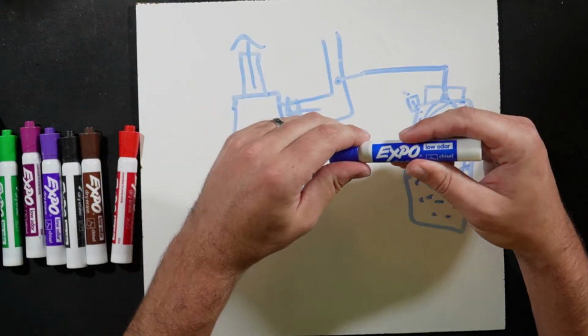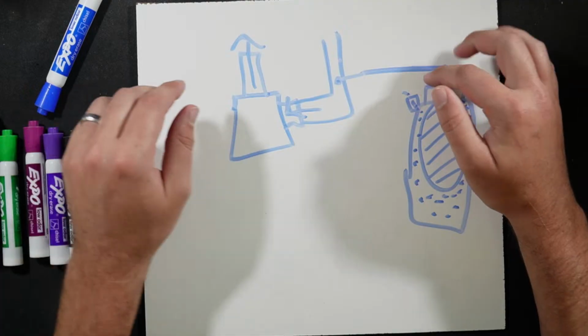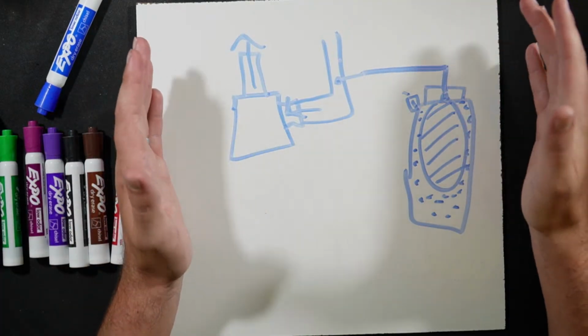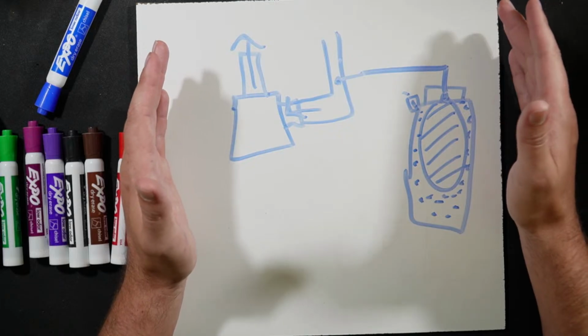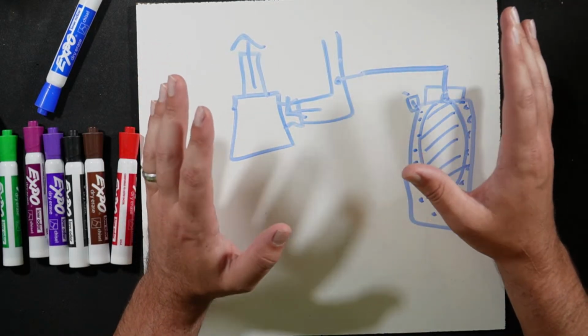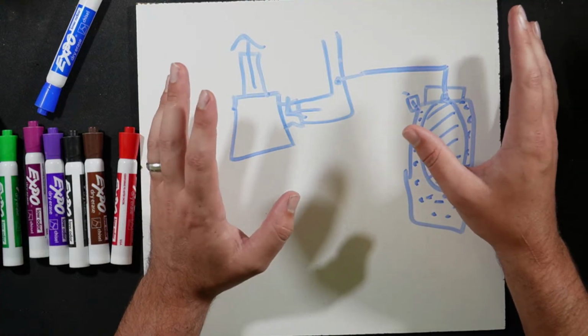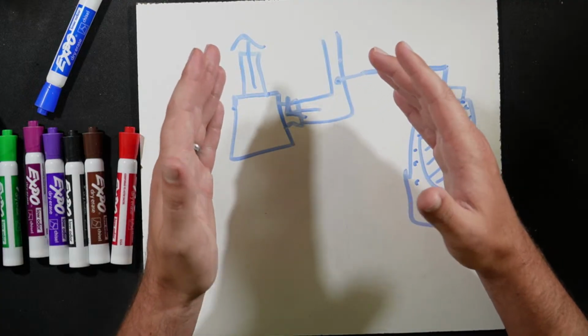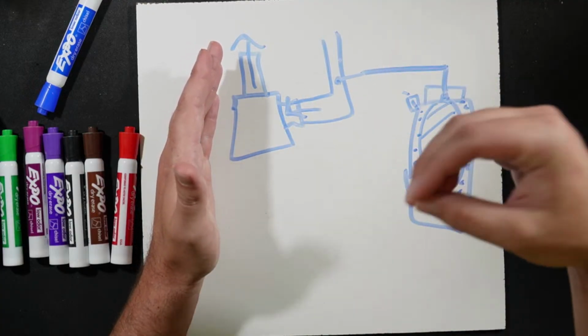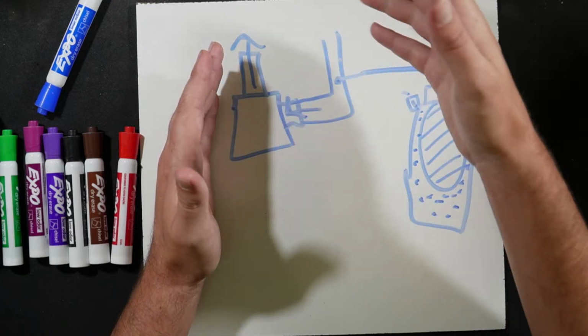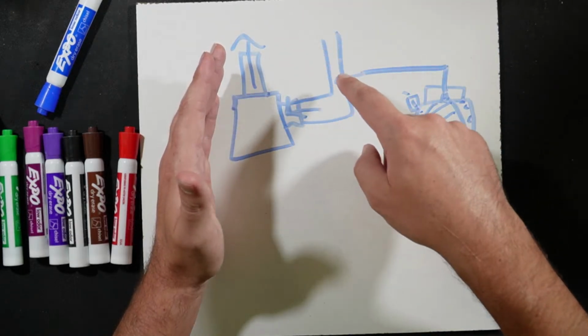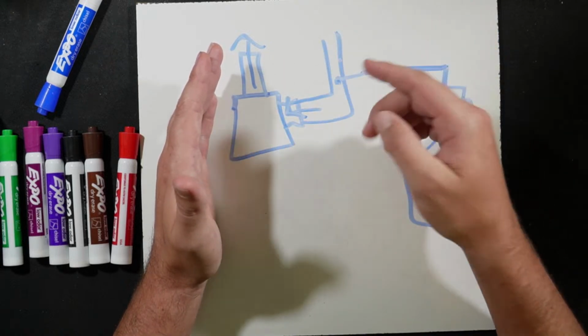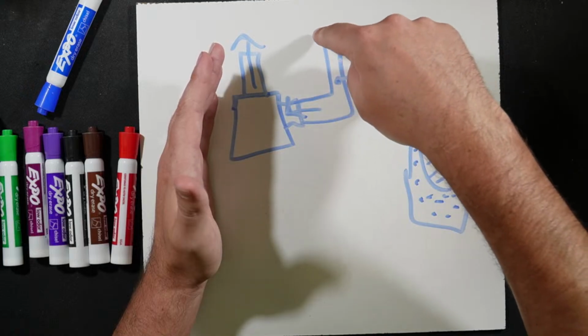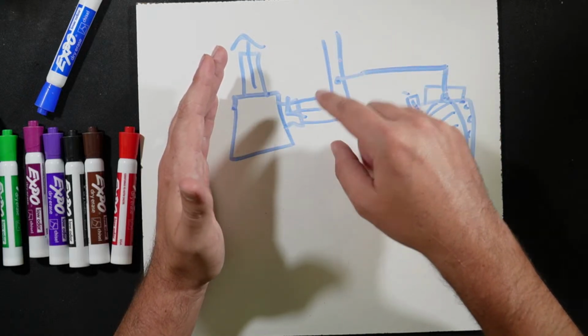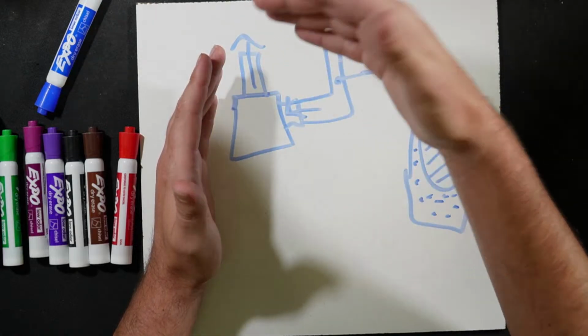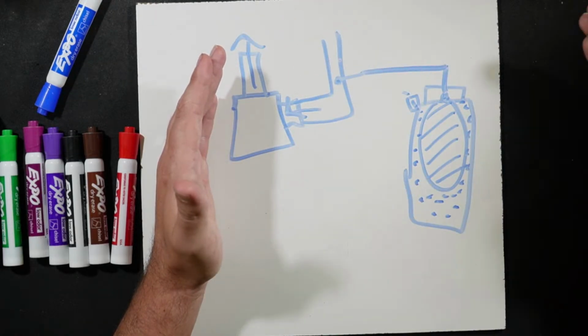One of the things, and this tripped me up for a long time, is that we want to set this tank pressure to what our loop pressure is desired to be, and we want to do that at the operating temperature. So if we have a loop that we expect to run 45-degree supply water through, and this pump is feeding into the chiller, and we had a 10-degree design loop, which would mean at load we would have roughly 55 degrees coming into here. Then that 55 gets pushed to the chiller, the chiller turns it to 45, and then it comes back out to the rest of the building.